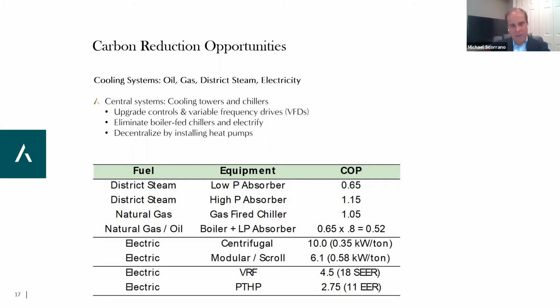If you look at the district steam one or the natural gas/oil slide, a lot of buildings were done with the technology available at the time for centrally cooling buildings. They would use Con Ed steam - low P means low pressure absorber - very inefficient air conditioning equipment that would take steam and through the cycle make cooling. The term we throw up as engineer geeks, coefficient of performance, just says how much energy in do I need, or how much energy out do I get for how much energy in?